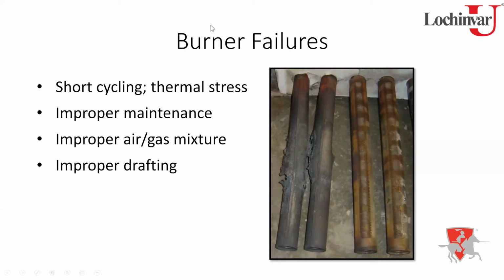Absolutely. Something else to keep an eye on, whenever you pull these burners out, I also want them visually inspected. So if you see some type of cracks, dents, big dents, voids, things like that, I don't want you to put that burner back into operation. What I want you to do is get a replacement burner. And then once you get that new burner in there, you're good to go, get it back into operation.